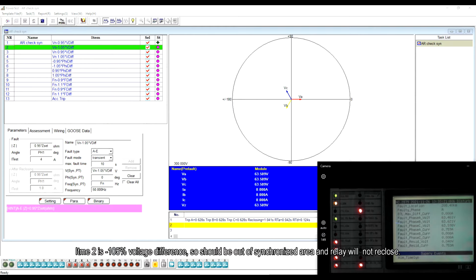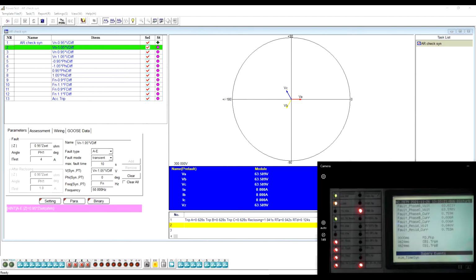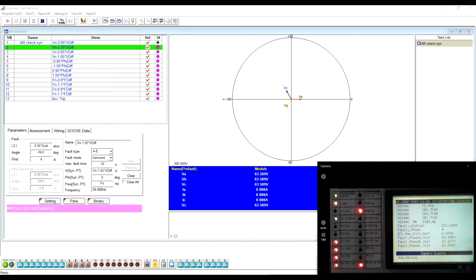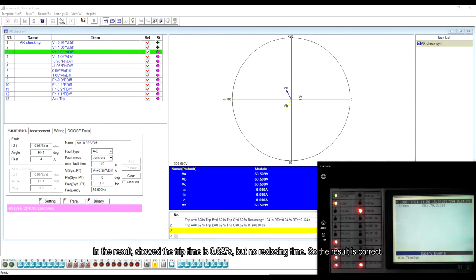Item 2 is negative 105% voltage difference, so should be out of synchronized area and the relay will not reclose. And in the result, showed the trip time is 0.627 seconds, but no reclosing time, so the result is correct.